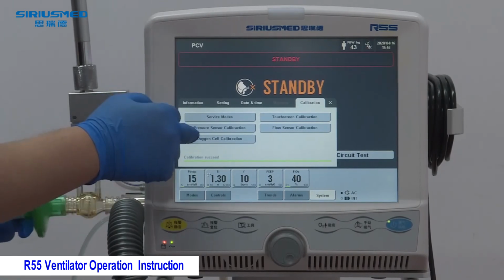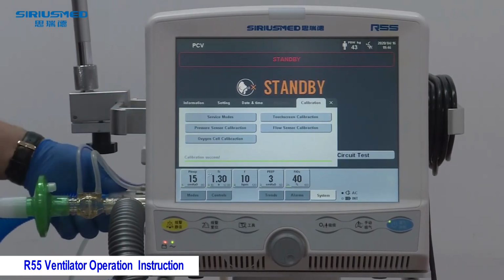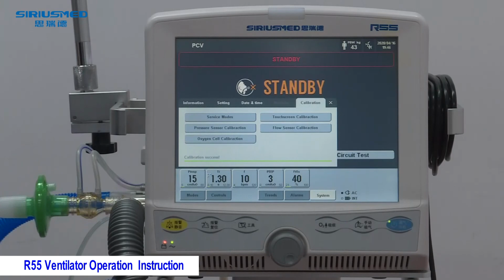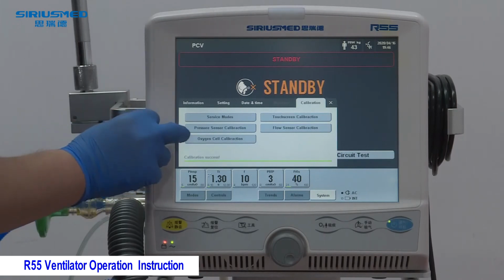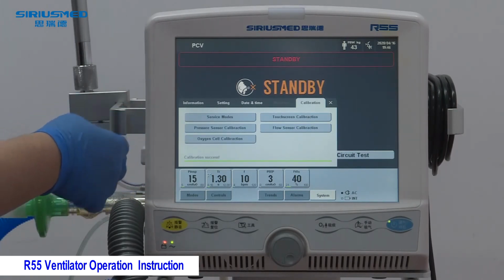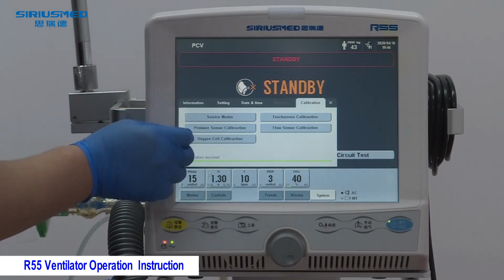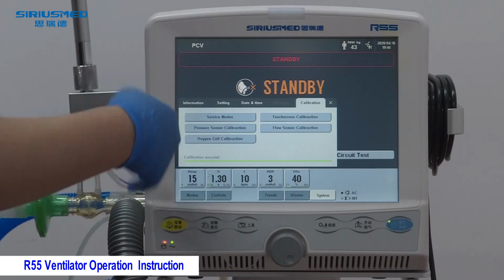And about the oxygen sensor calibration, this calibration is only used, for example, when the doctor changes the oxygen sensor, or when the FiO2 is abnormal, or the first time the ventilator is used. We need to do the oxygen sensor calibration. It's similar. Just click the oxygen sensor calibration, then it will be done automatically.